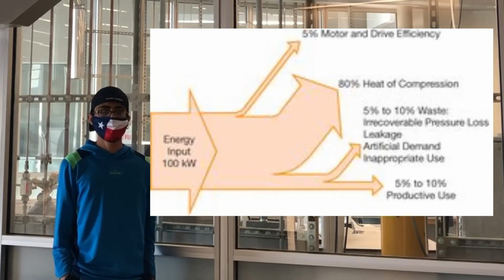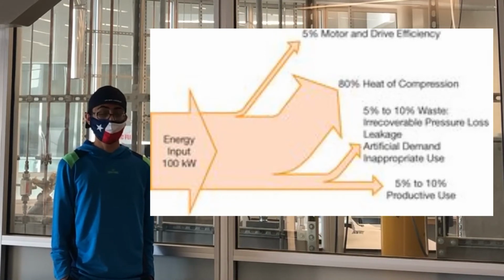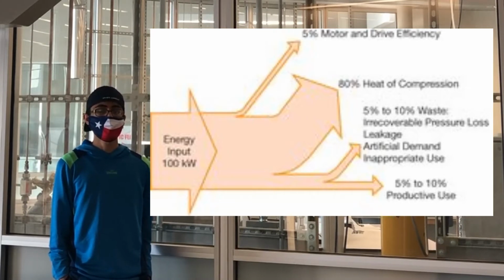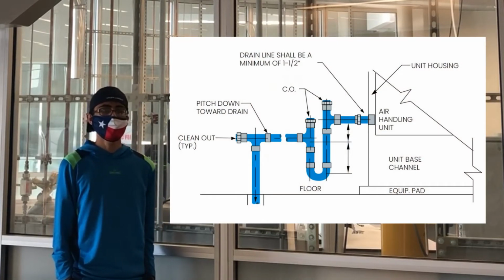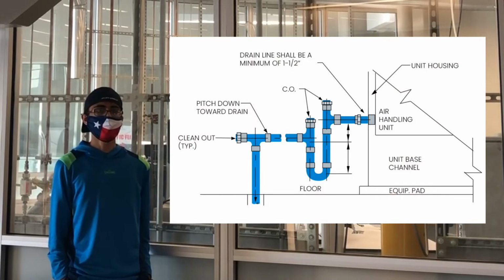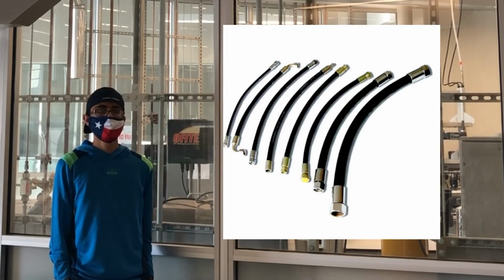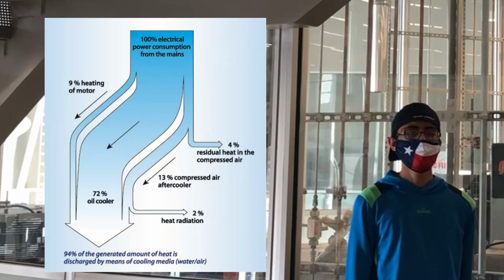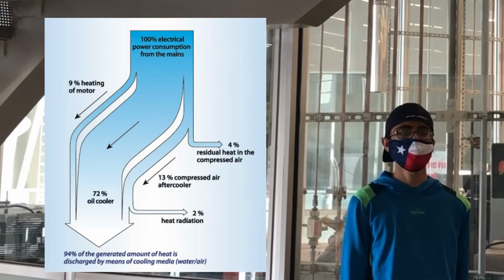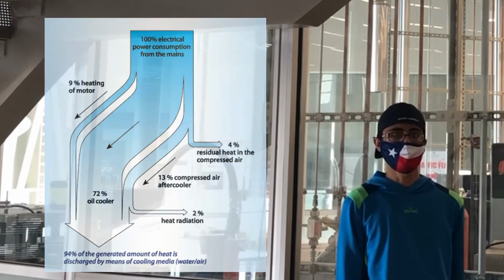These compressors should be maintained on a regular basis and should also run at a pressure that is not over the required pressure, as running over that can open the door for leaking pipes. The air compressor's condensate loss should be zero to ensure that the valves do not stay open and leak out compressed air. The air distribution through the compressor should happen through a short tube and one that is large in diameter to ensure that there is no pressure loss. Lastly, heat produced from compressors should be reused for businesses and consumers' benefit, such as heating water or distributing warm air to a room whenever necessary.